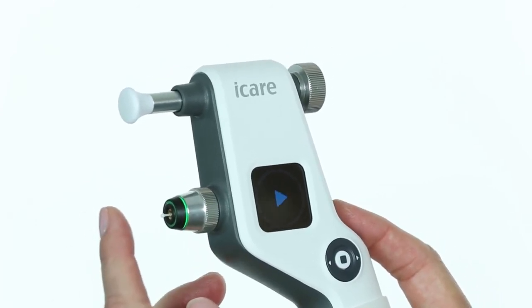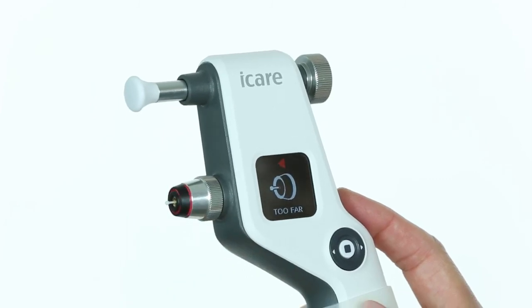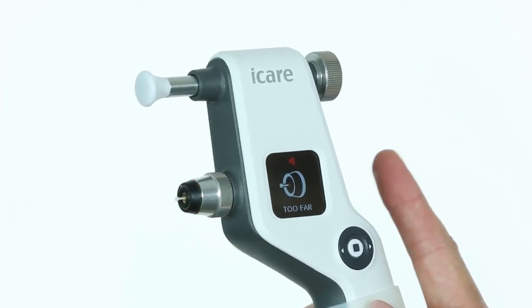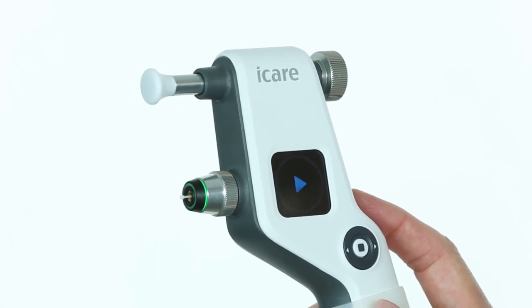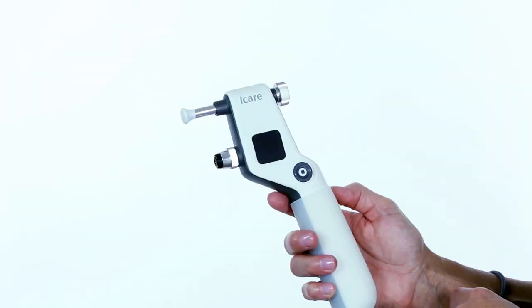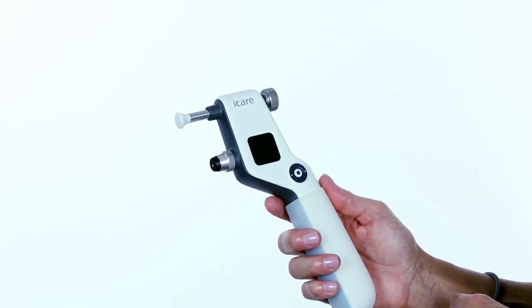If you are too far from the cornea, then too far will show in the display and the probe base light flashes red. Clear the error message, correct alignment, and continue measurement. If the tonometer is not used for three minutes, it will turn off automatically.